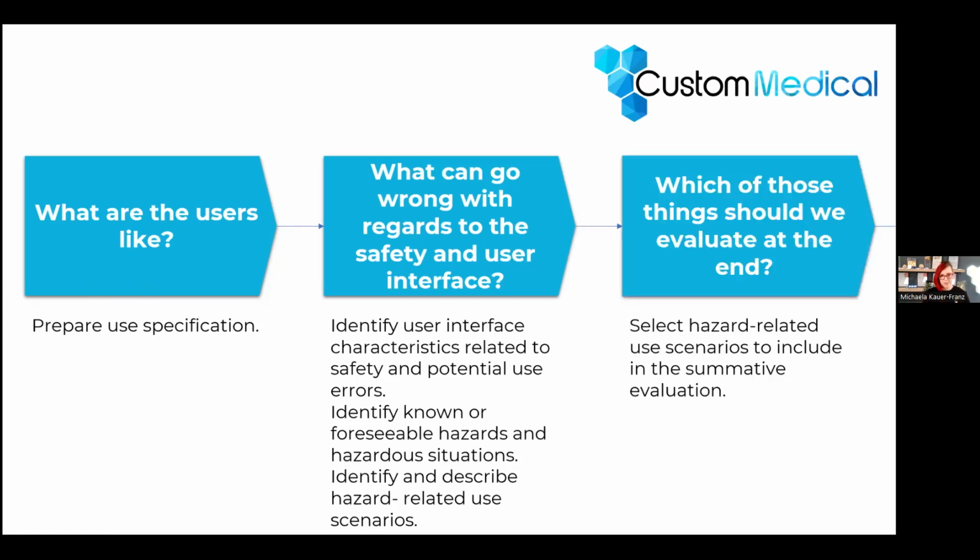In the next steps, you think about which of those things, so all the hazards that you identify and hazard-related use scenarios, you are going to evaluate in the end to show that your medical device is safe and free of unacceptable risk. Those are the scenarios that you have to include in your summative evaluation in the end.